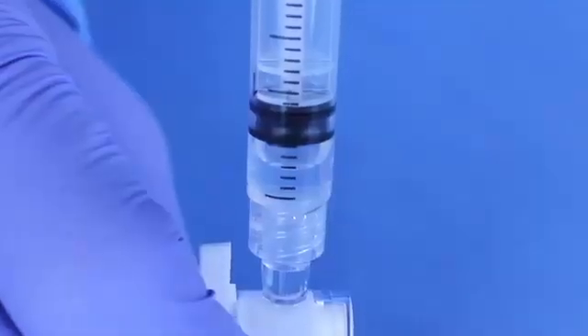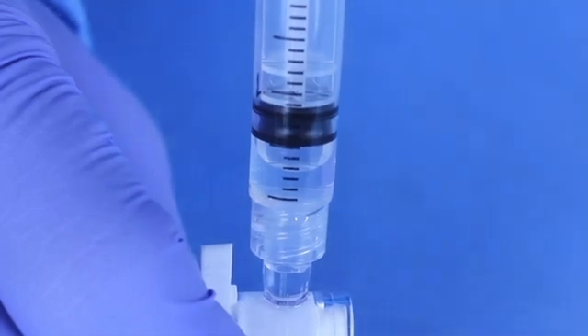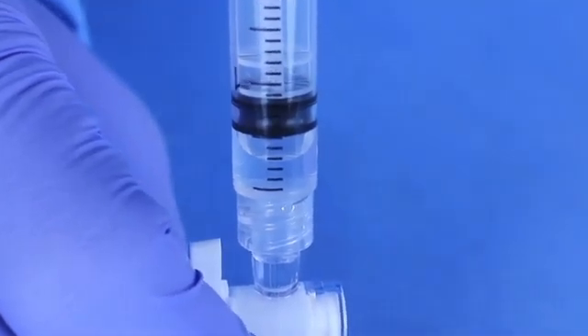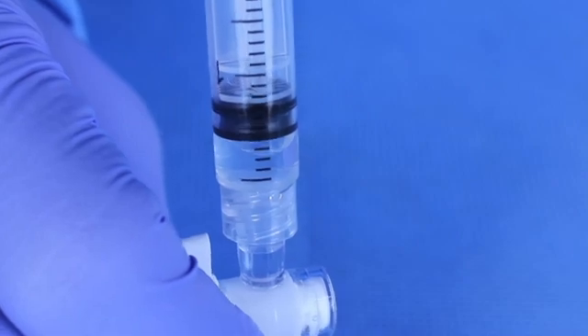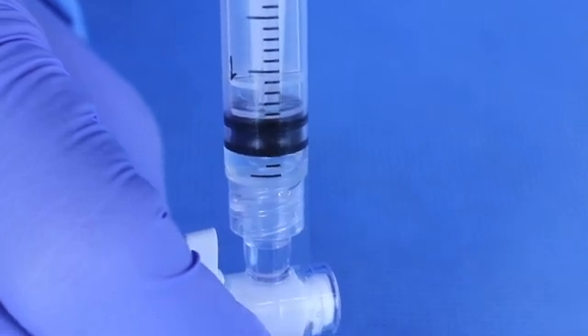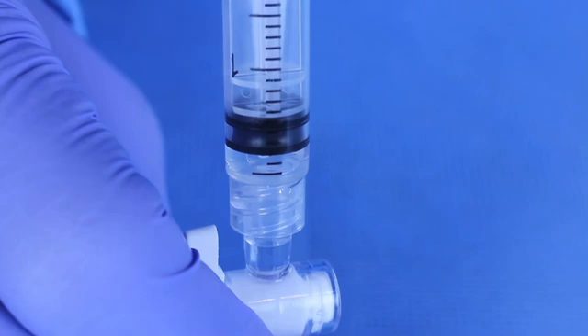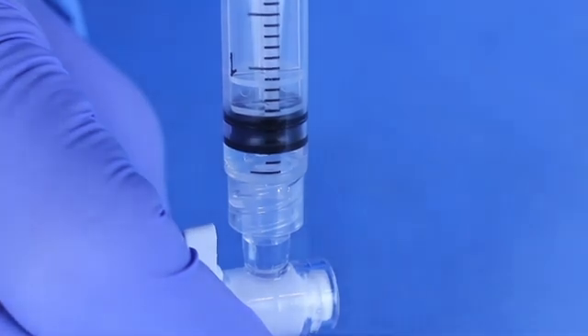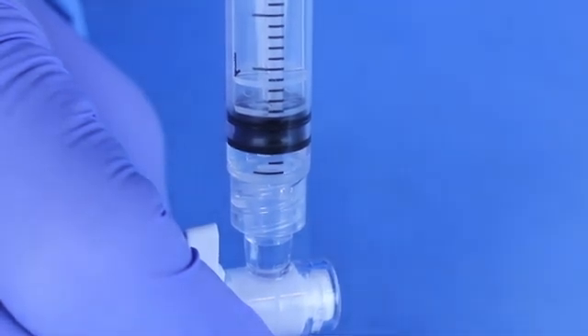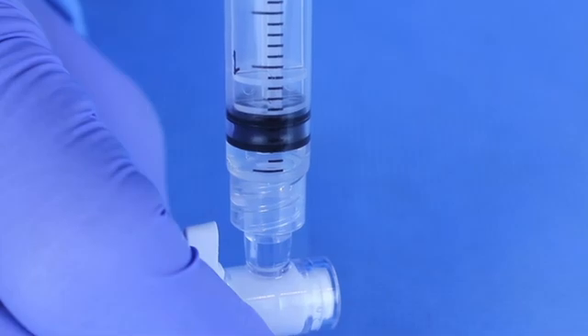When catheter is positioned in the cystic duct, note fluid level on syringe barrel. Inject 0.1 to 0.2 cc of fluid to inflate balloon approximately 6 mm in diameter. For larger cystic ducts, up to 0.6 cc may be used for balloon inflation. Maximum balloon diameter is 8 to 10 mm.